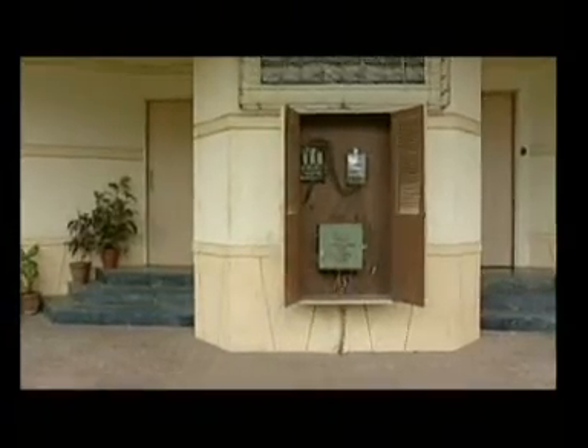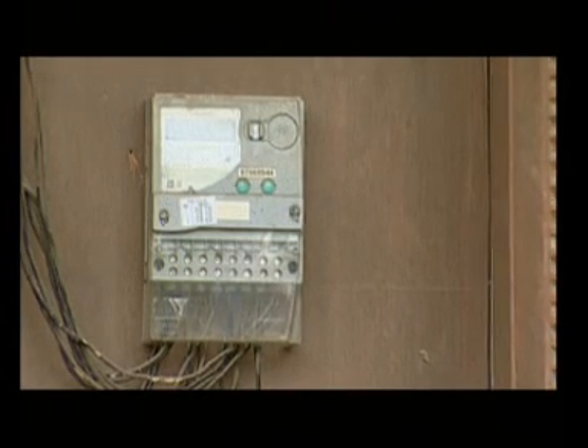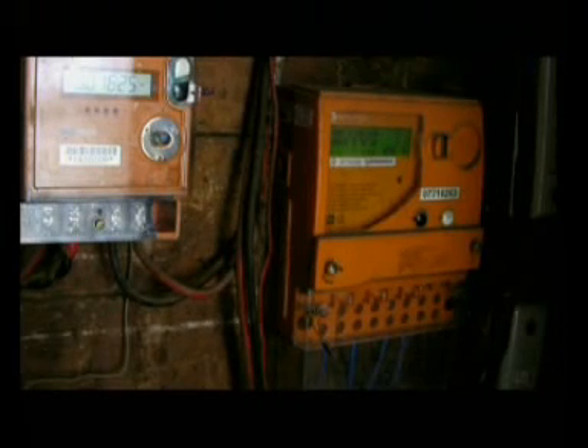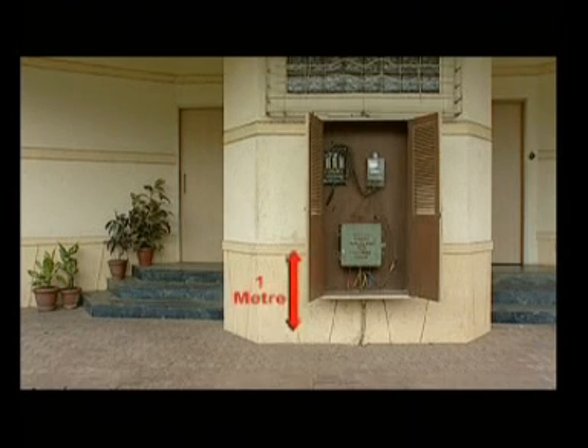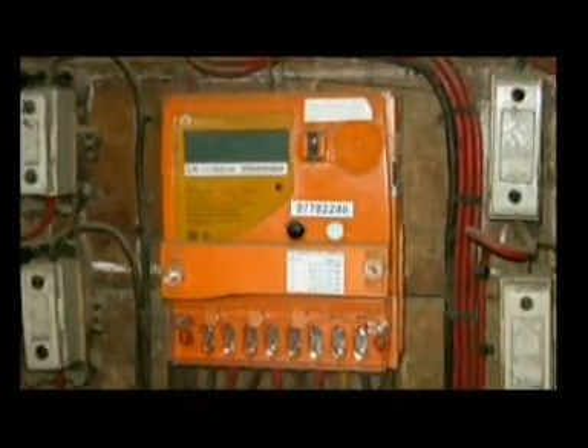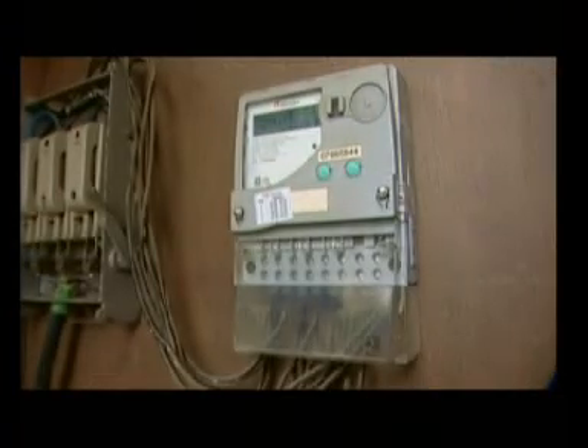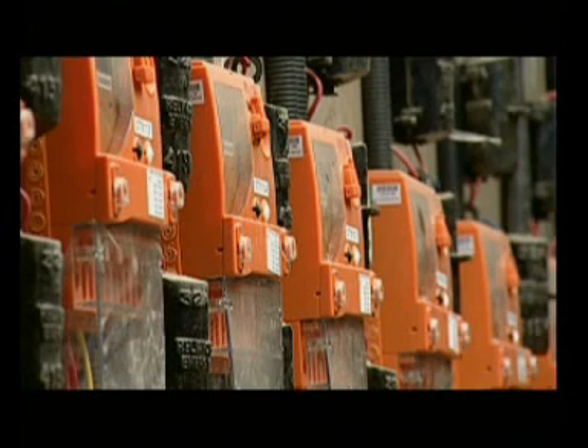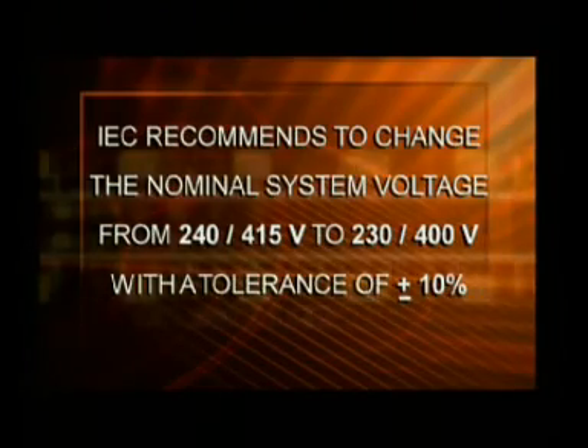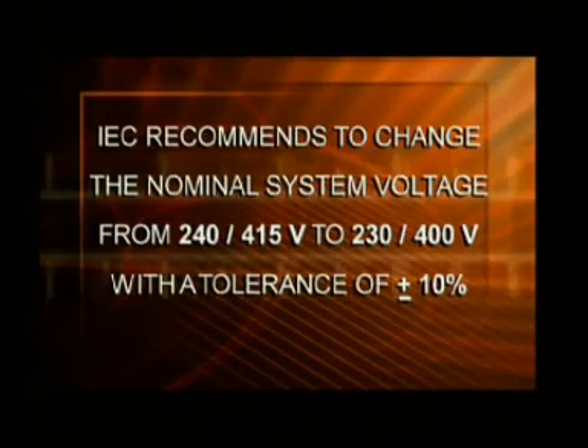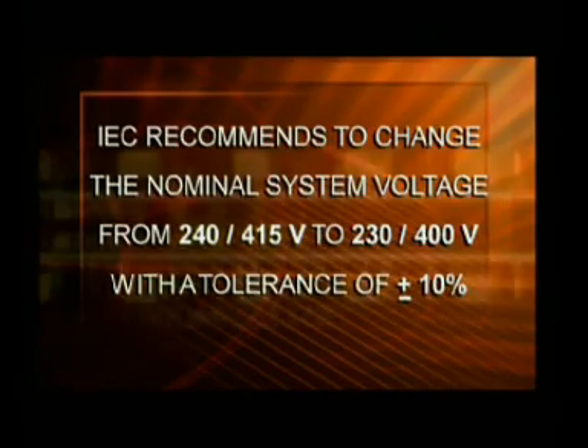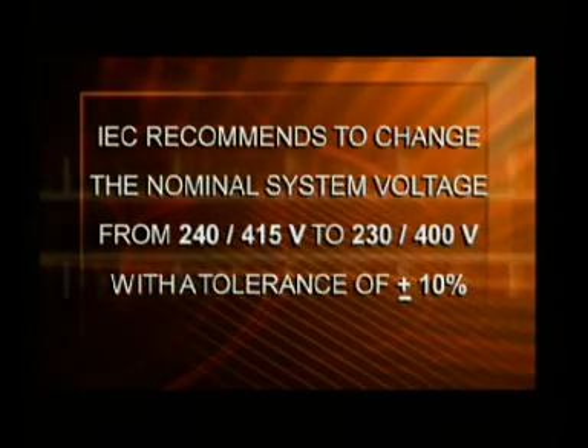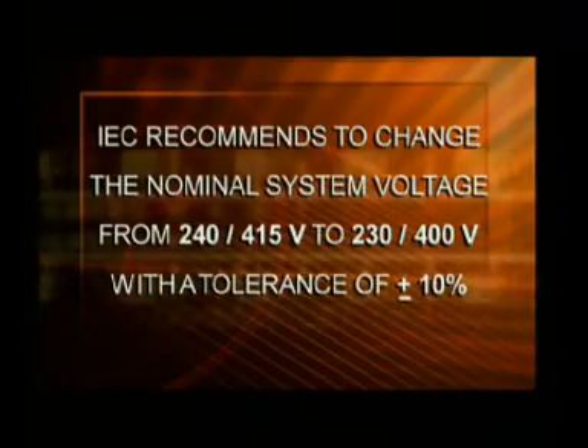As per the National Building Code of India 2005, the energy meters should be so installed that they are clearly visible and the readings can be taken easily. These meters should be at least 1 meter above the ground level. The energy meters should always be kept in a protective covering, either fully encased in glass or kept safely behind a closed door. In keeping with international developments, IEC has suggested revising the nominal system voltage from 240 by 415 volts to 230 by 400 volts with a tolerance of plus or minus 10%.